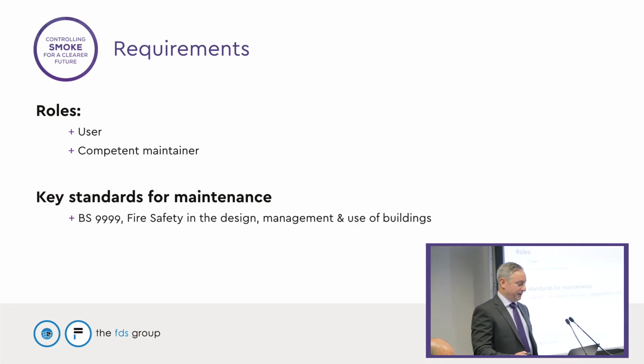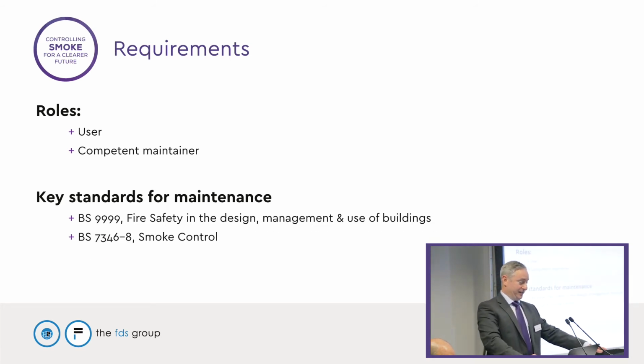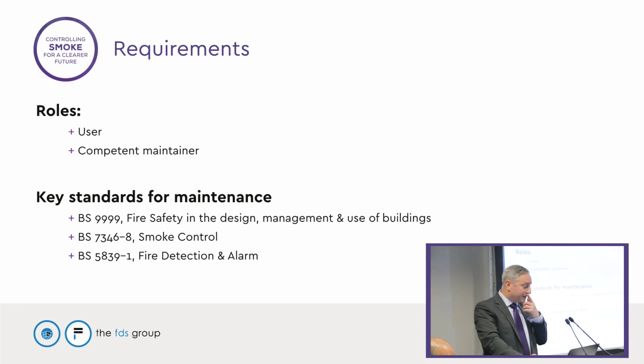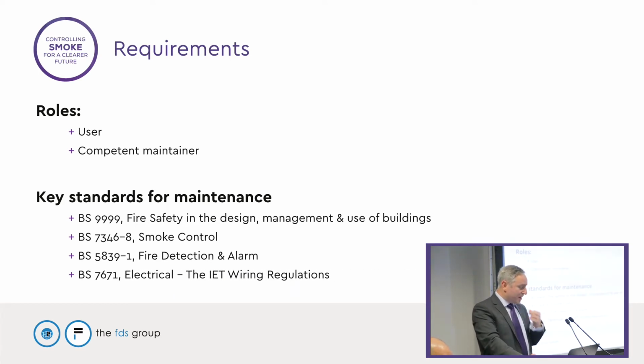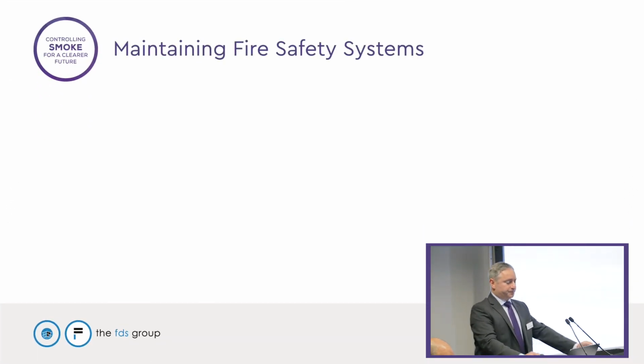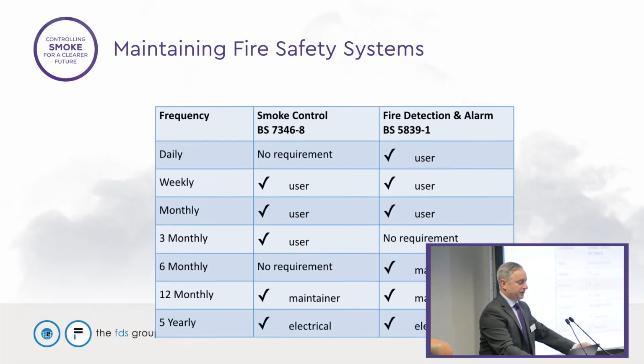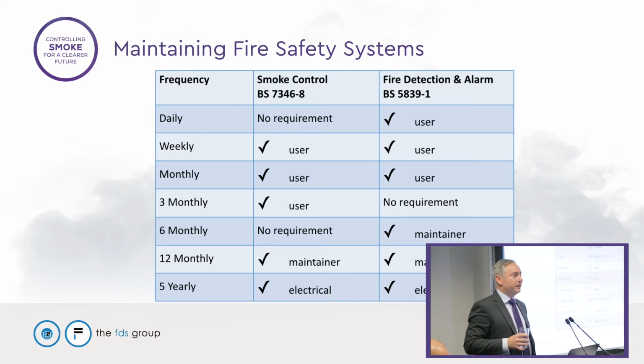And we have a number of standards we work to under maintenance, key one being 9999, because actually our smoke control standard says go read 9999 with a few extra bells and whistles on there. For fire detection, we have 5839 that specifies how we maintain a fire alarm system. It follows a similar theme to 9999, and even 9999 points back to 5839 saying do all these checks. And I mentioned earlier about a system being an electrical distribution system as well. It's an electrical network, so it also needs testing and maintaining in terms of electrical safety. So we introduced the wiring regulations, and their general basis is 5-yearly testing as well as commissioning tests. So this is a rough outline of what's expected to be done during the life of building and your systems.